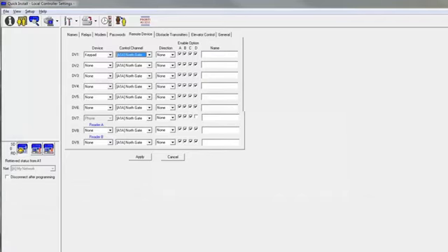We also have a card reader wired to Reader A, or the DV8 input on the AM3 panel. Our cards are 26-bit, so we will want to select Wiegand 26 for DV8.